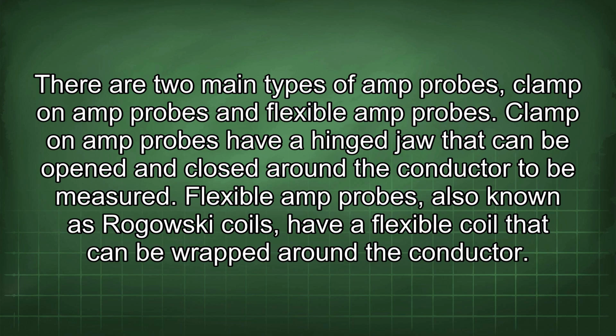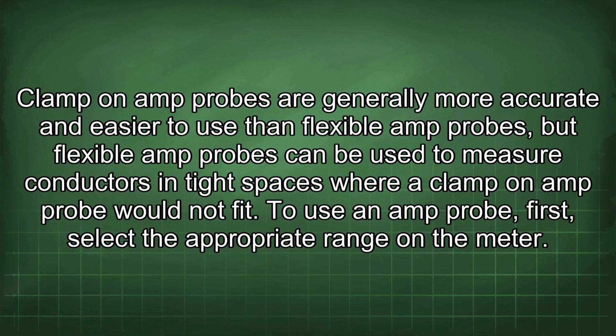Clamp-on amp probes have a hinge jaw that can be opened and closed around the conductor to be measured. Flexible amp probes, also known as Rogowski coils, have a flexible coil that can be wrapped around the conductor. Clamp-on amp probes are generally more accurate and easier to use than flexible amp probes, but flexible amp probes can be used to measure conductors in tight spaces where a clamp-on amp probe would not fit.